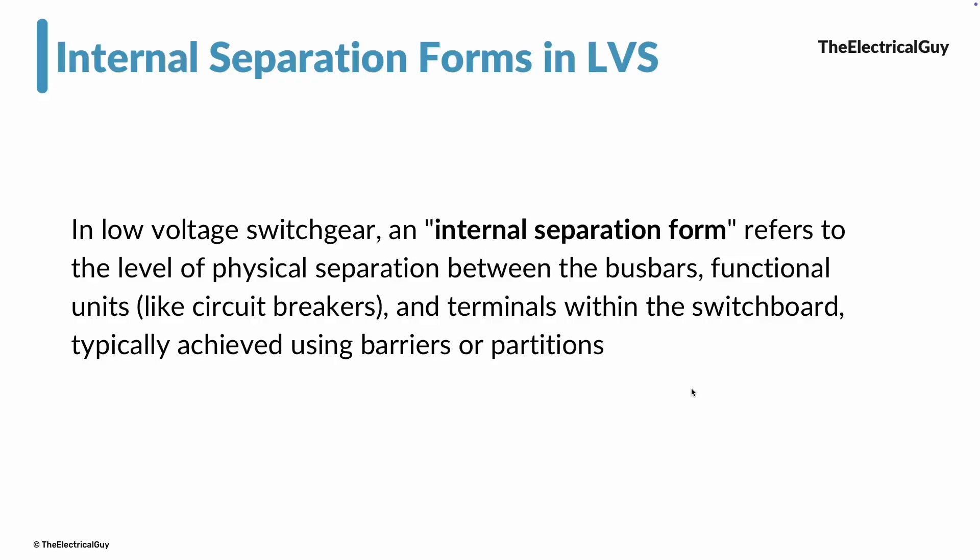Let us understand what an internal separation form is. In low voltage switchgear, an internal separation form refers to the level of physical separation between the busbars, functional units, and terminals within the switchboard, typically achieved using barriers or partitions. So, as the name suggests, we use separation forms to separate the different components of the low voltage switchgear.